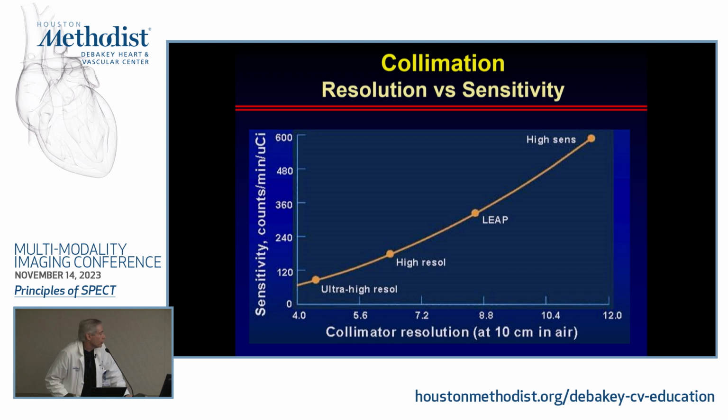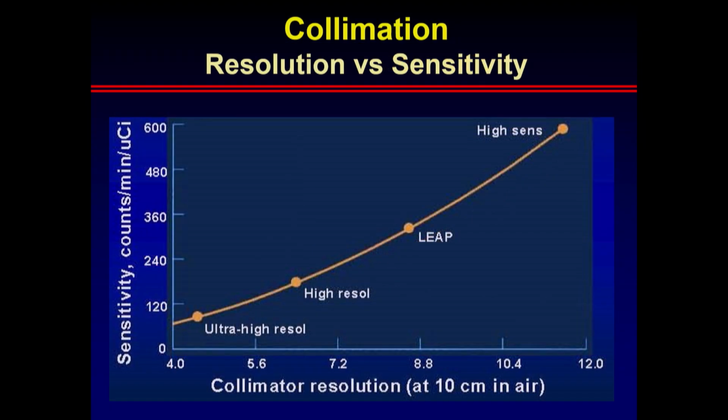This is also the situation when looking at different types of collimators, and at sensitivity and resolution. You can see that they're basically inversely related. The very high resolution collimators have very low sensitivity, but look at the spatial resolution. It's actually great. Whereas high sensitivity collimators, which have very wide bores and very short septa, acquire a lot of counts, but unfortunately the resolution will be quite bad.